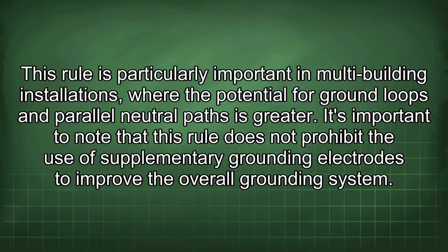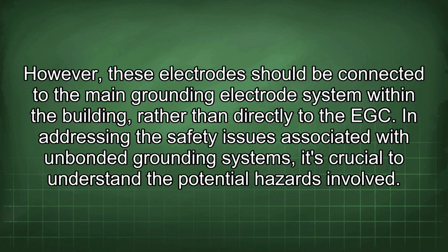This rule is particularly important in multi-building installations where the potential for ground loops and parallel neutral paths is greater. It's important to note that this rule does not prohibit the use of supplementary grounding electrodes to improve the overall grounding system. However, these electrodes should be connected to the main grounding electrode system within the building rather than directly to the EGC.